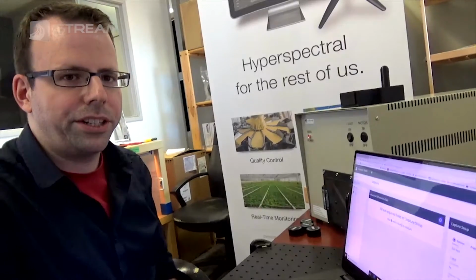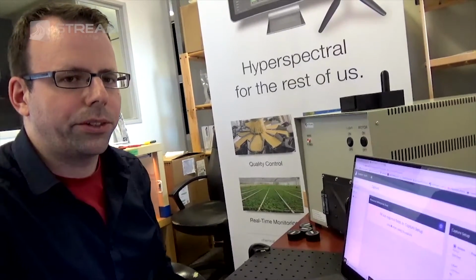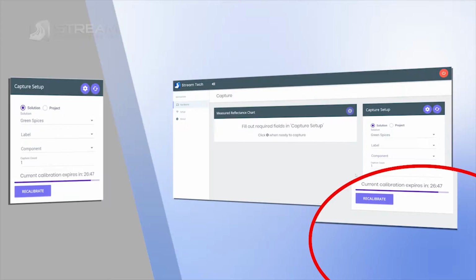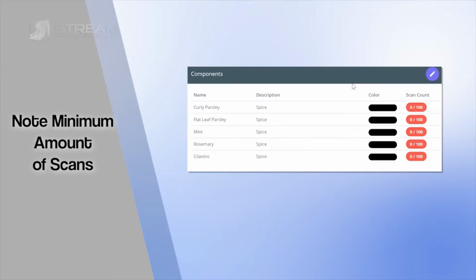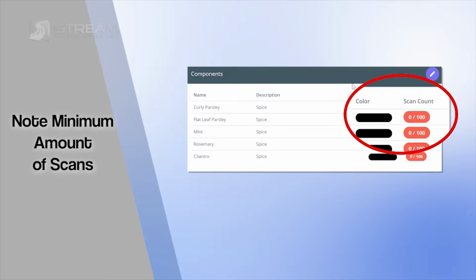Once you finish the calibration, you'll have about a half an hour before you have to recalibrate again. This limit is enforced because spectrometers have drift that can cause them to change in behavior over time, mostly due to temperature changes or other sorts of things like that. One thing though is the solutions. Basically, for each component, we enforce a minimum amount of scans to be 100.